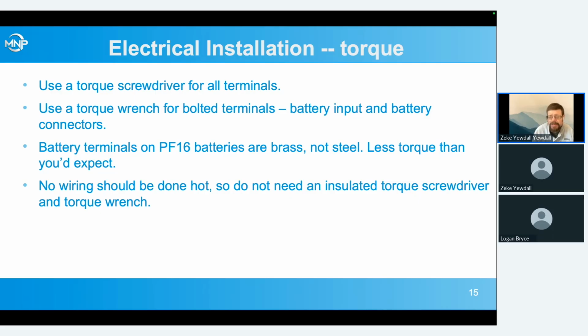And best practice when torquing is to torque it, wait a bit, an hour or two, and then go back and check it again, because some wire types will relax a little bit under pressure, and then you'll need to torque them again. And that's better than just cranking the heck out of them the first time and calling it good.